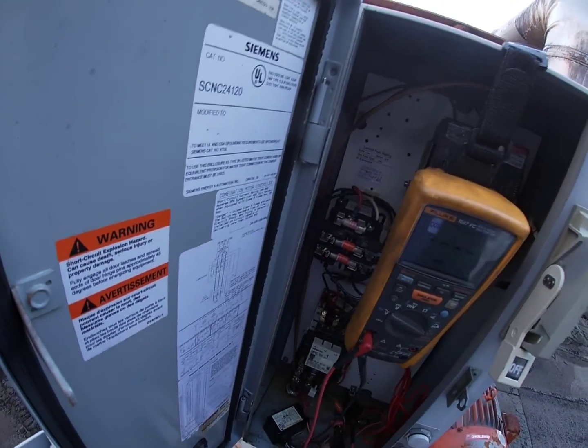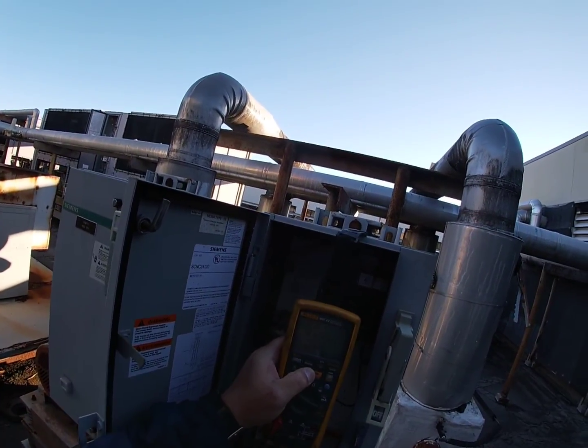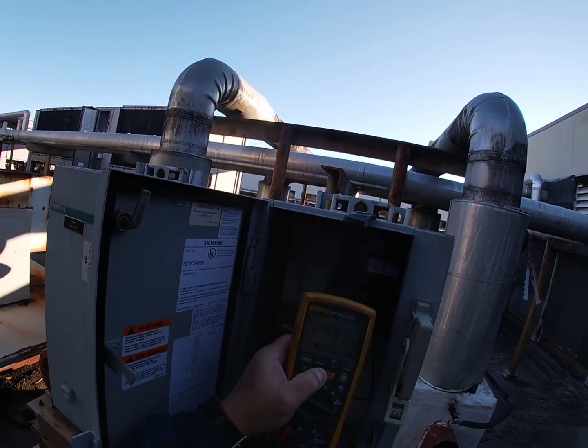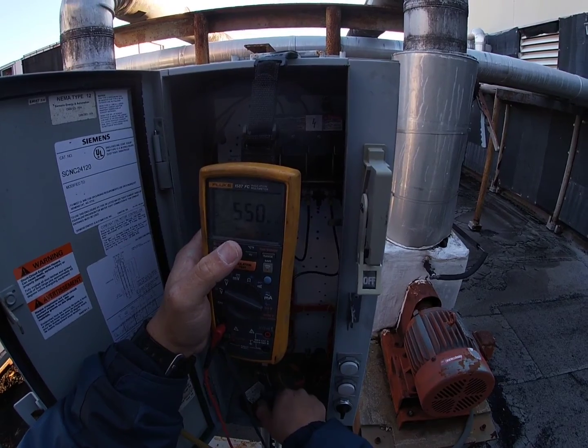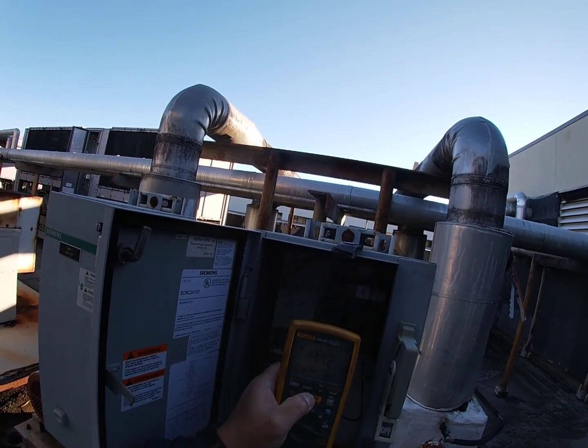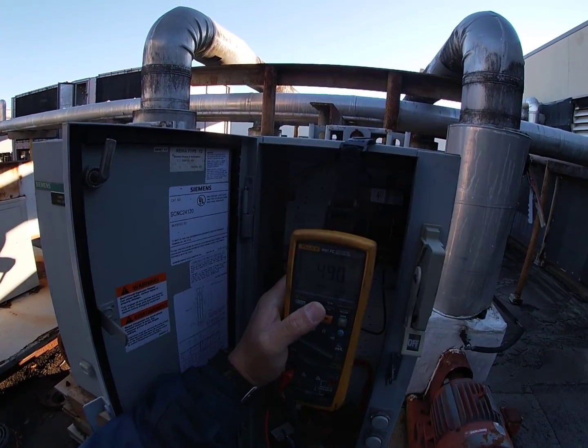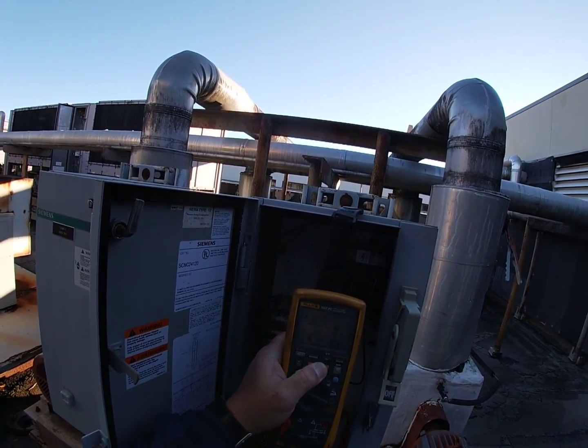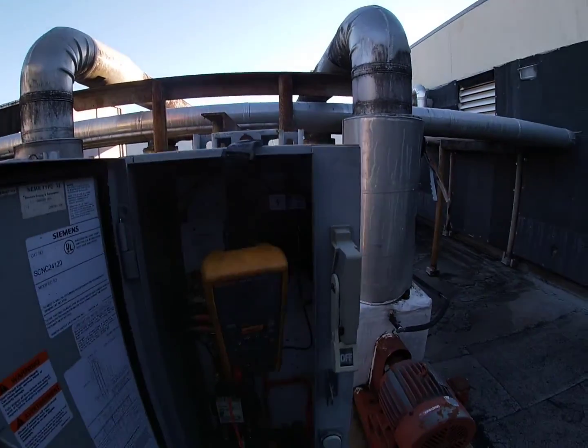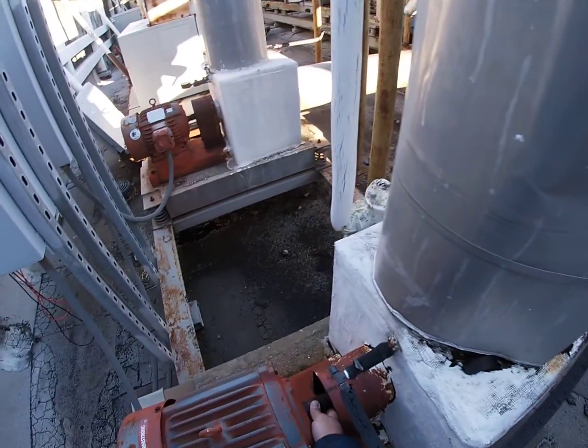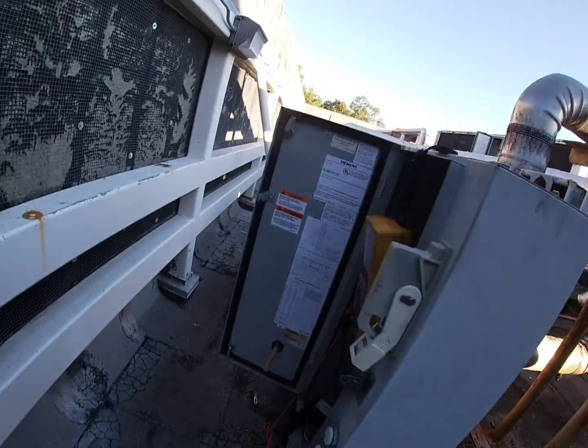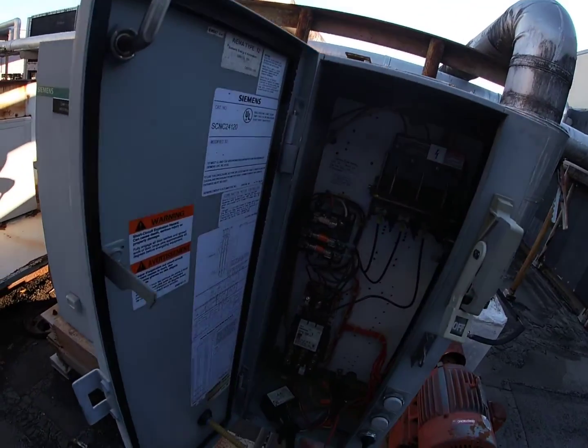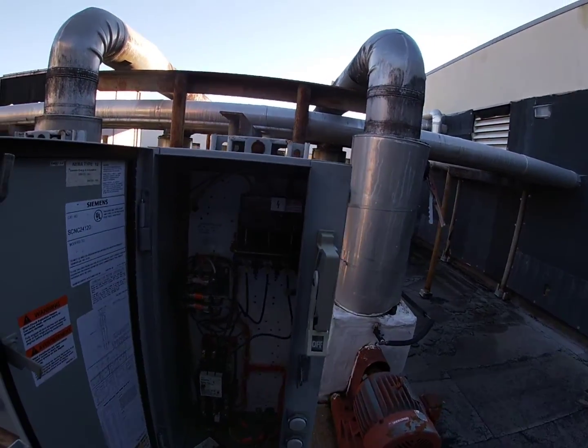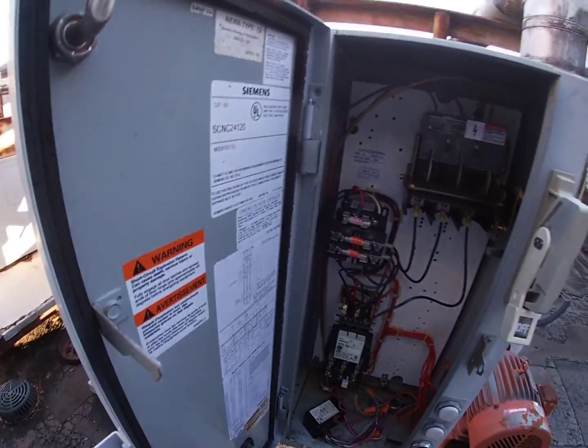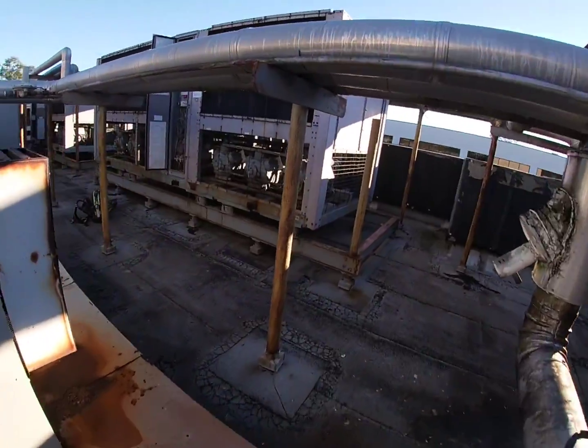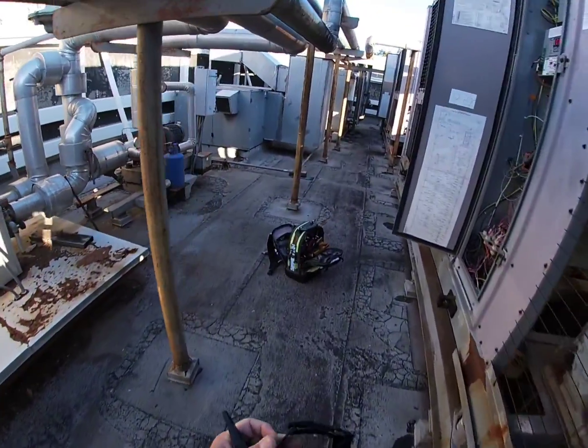If I'm good here, then I'm not going to do that because those wires are already going there anyway. So let's go ahead and apply voltage to it. It's taking my voltage and we're good on that leg. Same thing, we're good here. I think everything's okay with that motor. We're good. And like I said, the motor does move freely. It almost sounded like it was locked up when it was losing a phase, which is kind of what it would sound like. But anyhow, we're good here. We're just gonna get them a new contactor and we'll be good to go. A new starter. Actually, I'm gonna replace the whole starter on there. We're good to go.